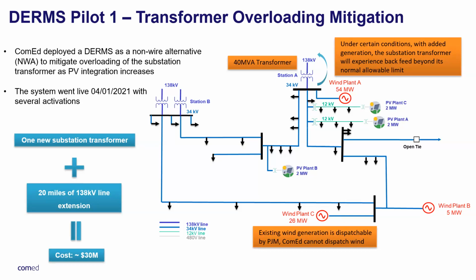On the right is the one-line diagram showing the transformer stepping down from 138 kV to 34 kV in the distribution substation. We have a 40 MVA transformer, and a lot of wind generation in the field, which means that during normal operating conditions, it's very likely to backfeed into the system—something we've already been seeing for some time.